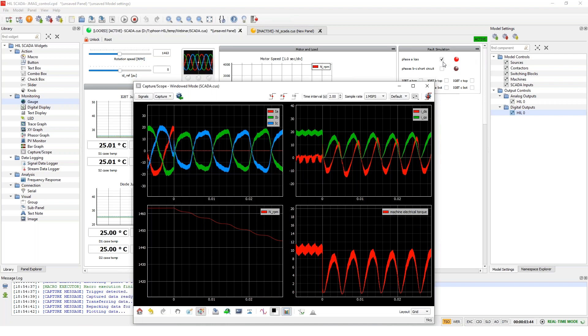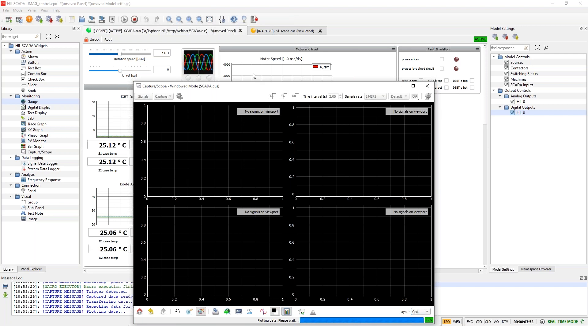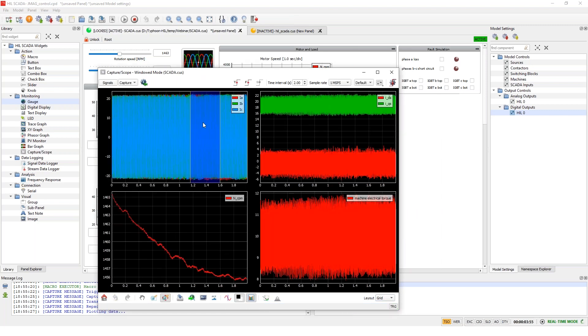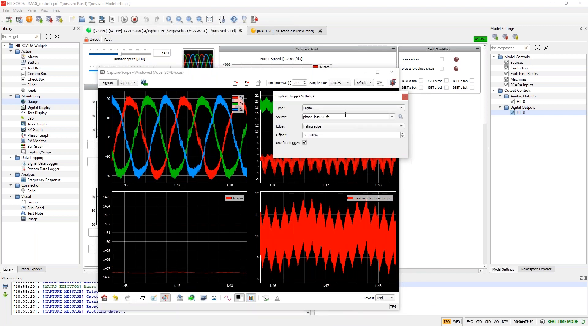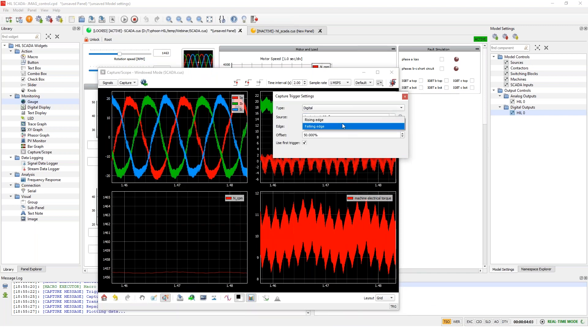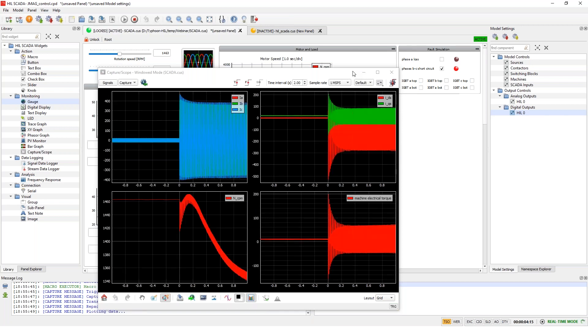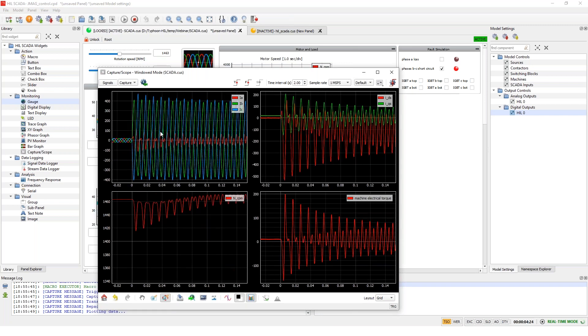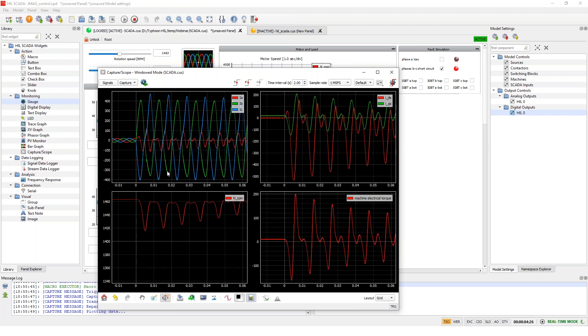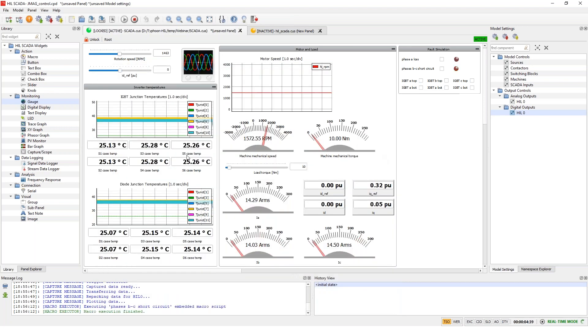Okay, I'm going to go back to normal state. And again, just capture the signals to see if everything's fine. Okay, so I'm back here, and maybe I'll just also trigger on the short circuit contactor, just to see what happens when we introduce a short circuit. Okay, and again, okay, sorry, so this is where our short circuit occurs. And we can see again that the controller doesn't actually react to it in any particular way. Okay, clear all the faults.